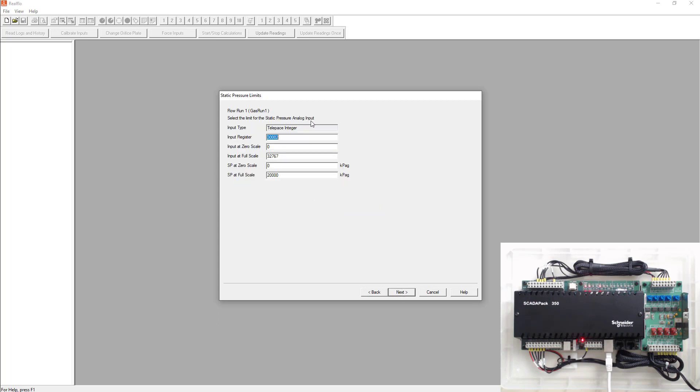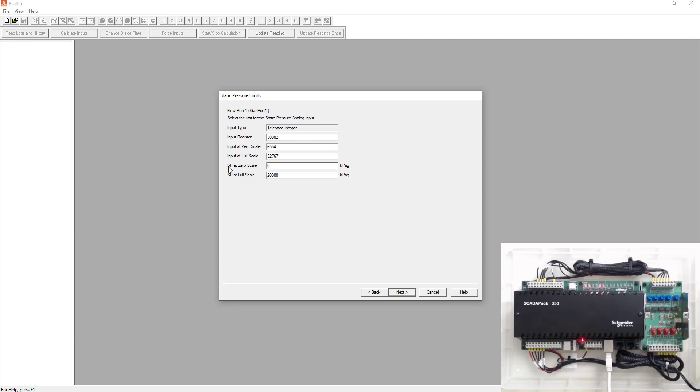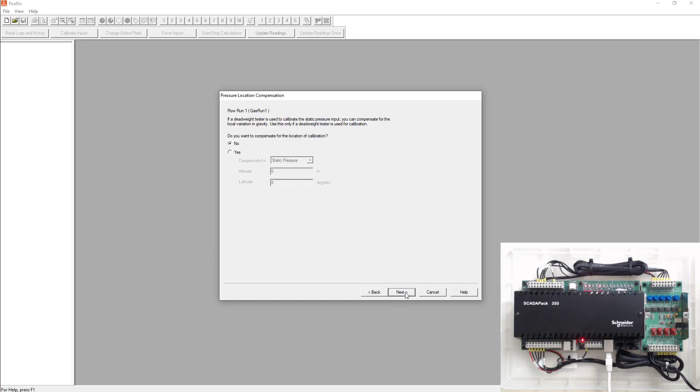Next it's going to ask you where is your static pressure analog input coming. So we know we use 300001 for the differential pressure. So we use the next analog input, which is 300002. We know that it's scaled from 6554 to 32767. For this static pressure, we're going to pretend it's scaled from 0 to 20,000 kPa. Select next.